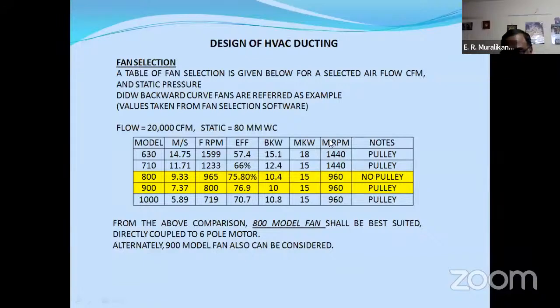But here is what people actually are not aware of. You know, we have two pole, four pole, six pole, eight pole. Four types of motors are available. Eight pole is 720 RPM, six pole is 960, four pole we are aware, 1440, and 2850 is two pole. So not only the fan selection, even the motor selection, that particular pole, 2, 4, 6, 8, also has an impact on the energy saving potential. If I have a 1440 RPM motor, and unnecessarily put a pulley and increase my friction loss, then the fan selection will be of no advantage for me. So here is where we are able to see energy saving.